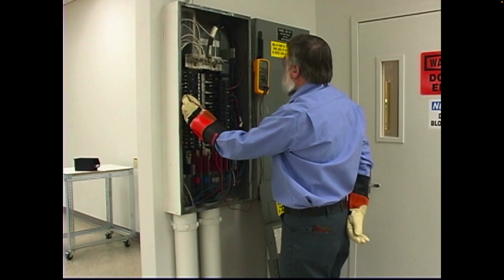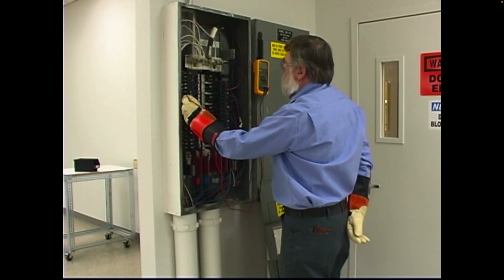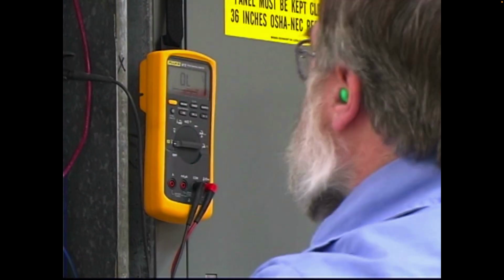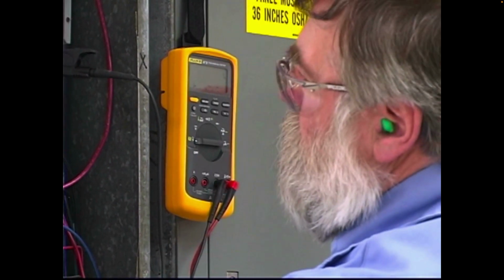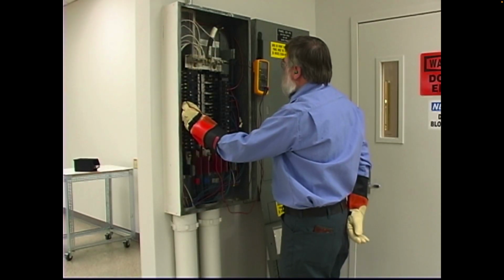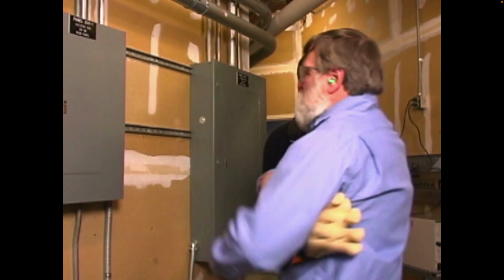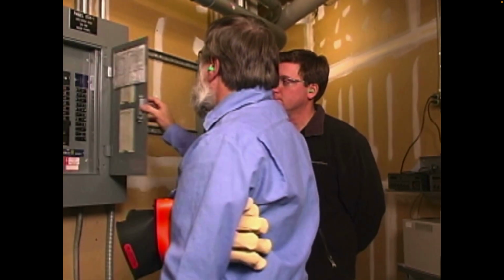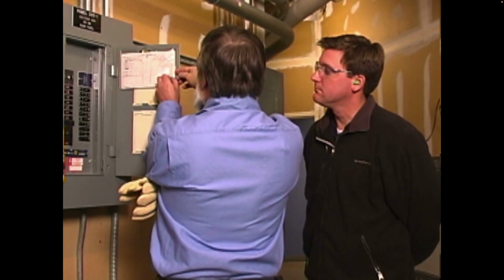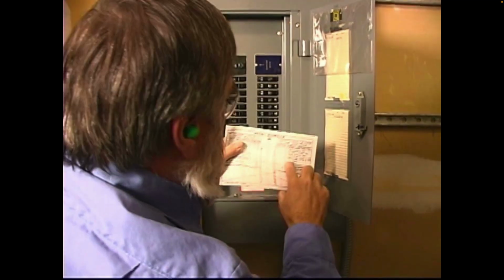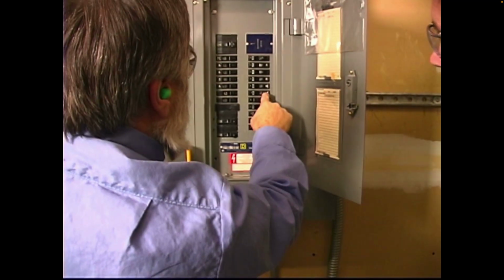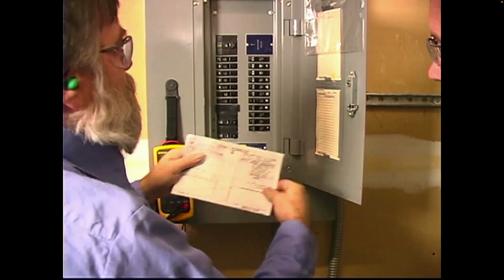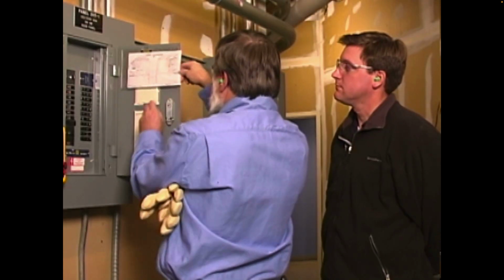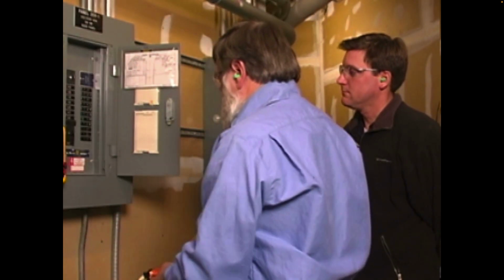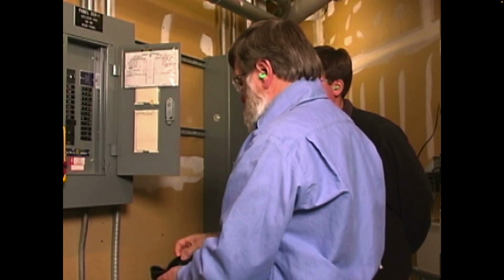Try to follow the old electrician's advice. Whenever you can, keep one hand in your pocket, but use common sense. Sometimes you need both hands to make a good measurement. The safest place to measure voltage is where the lowest energy is available. For example, if you're measuring voltage on a breaker panel, identify the lowest rated breaker available and make your measurement there. This way, you have more protection between yourself and the potential hazard.